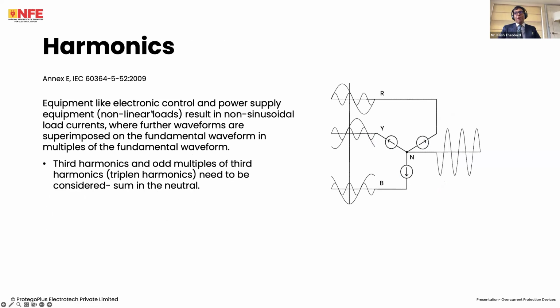Harmonics. The most significant ones are triplen harmonics. So we talk about red, yellow, blue. Okay. Phase L1, L2, L3. Because we have equipment like electronic control and power supply equipment, this results in non-sinusoidal, distorted load currents, and there are further waveforms superimposed on the fundamental waveform. These are in multiples of the fundamental frequency. So this is 50 hertz. This may be 150 hertz, for instance. Thing is, normally, if they're 50 hertz and they're all 120 degrees apart, they will all cancel out. However, because these are times three, they will sum. So effectively we have this adding, and we have current flowing in the neutral conductor.